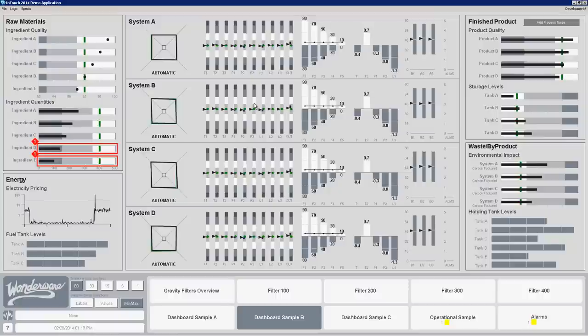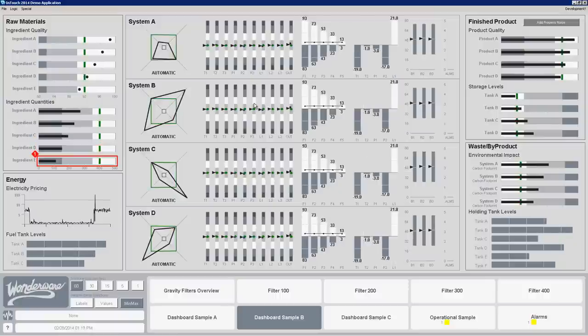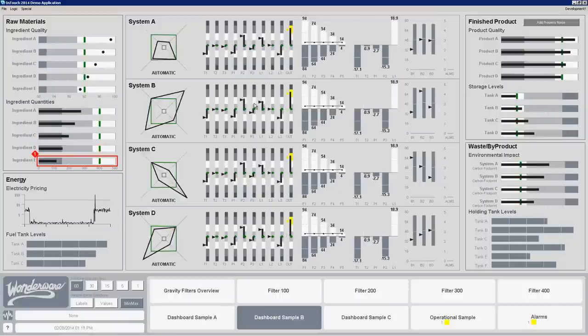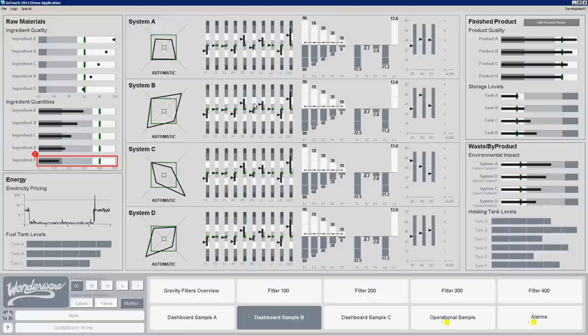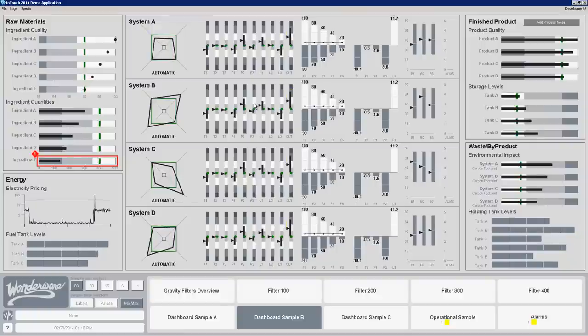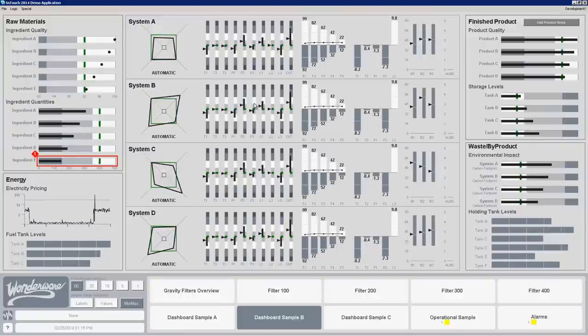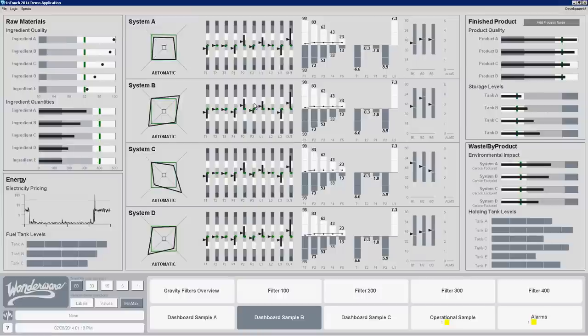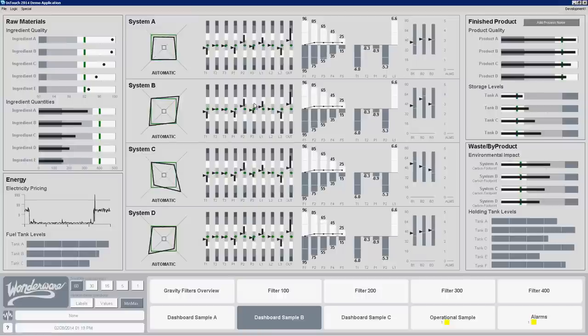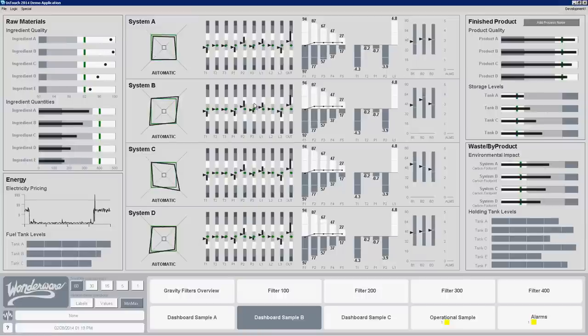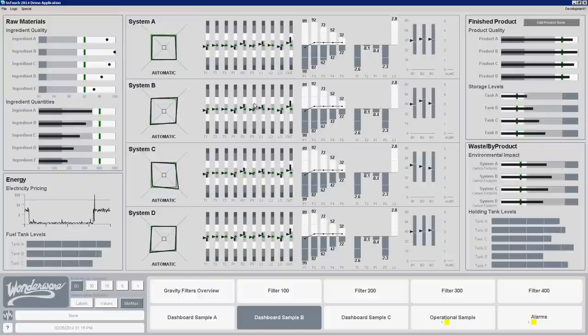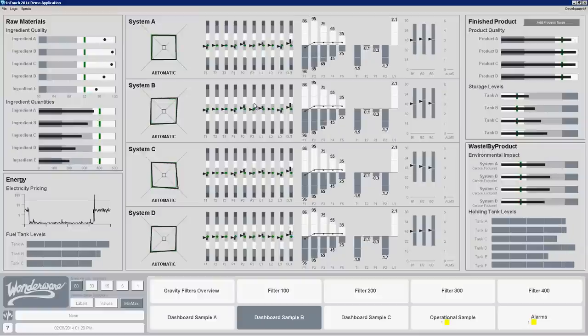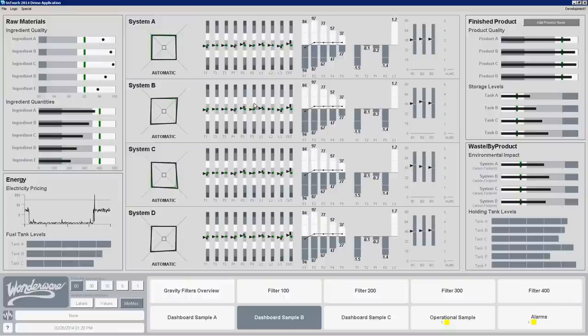When I'm looking at my overall process I don't need to see all the pipes and valves and pumps and motors. I've seen that done before where my major overview just shows me every piece of equipment in one massive overview screen. That's usually a recipe for disaster when I've seen it done in that way. But really what's been trying to be done here is to provide an overall view of that process and an overall indicator of what's going on and try to use some of these contemporary dashboarding mechanisms to allow you to convey that information in a very human readable format.